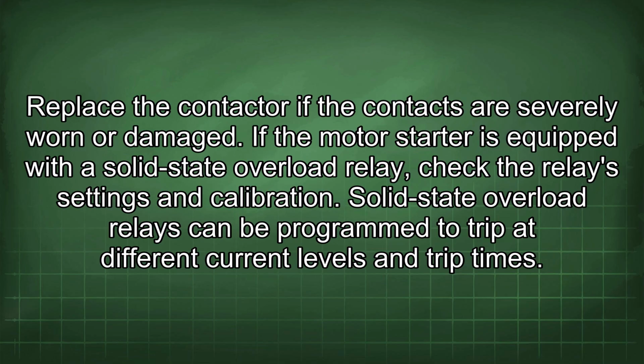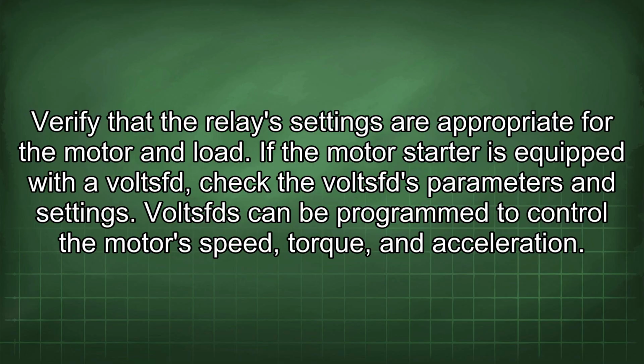If the motor starter is equipped with the solid-state overload relay, check the relay's settings and calibration. Solid-state overload relays can be programmed to trip at different current levels and trip times. Verify that the relay settings are appropriate for the motor and load.